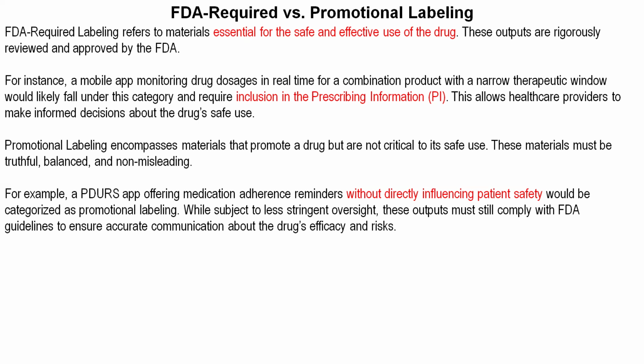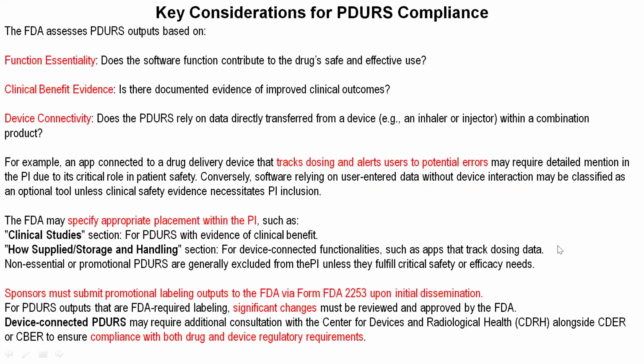So whether it's mandatory or not depends on whether they directly influence patients' safety. So what is the FDA thinking about in compliance? They look at the output and the functional essentiality.